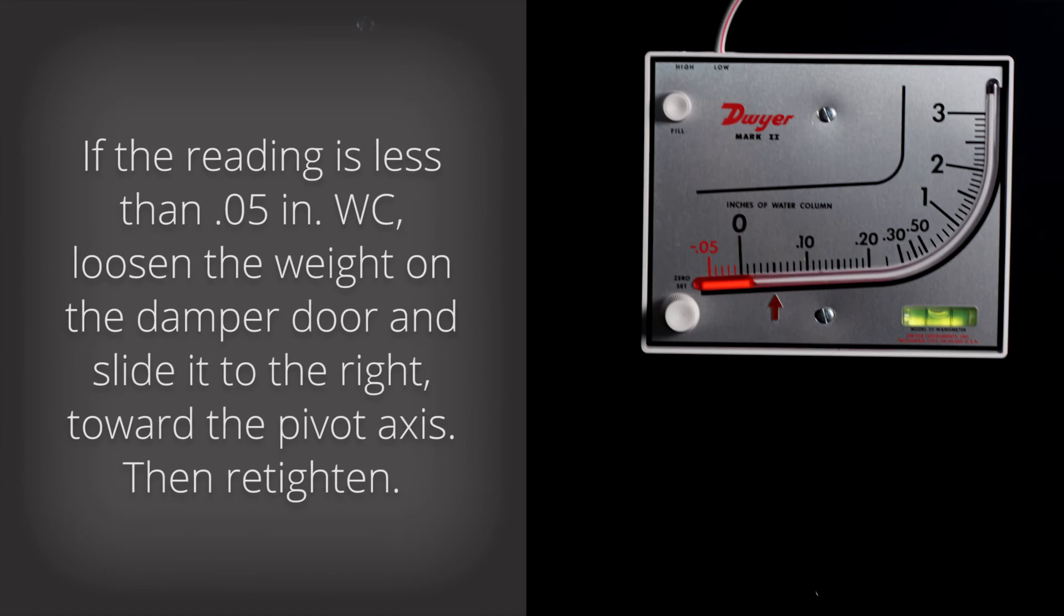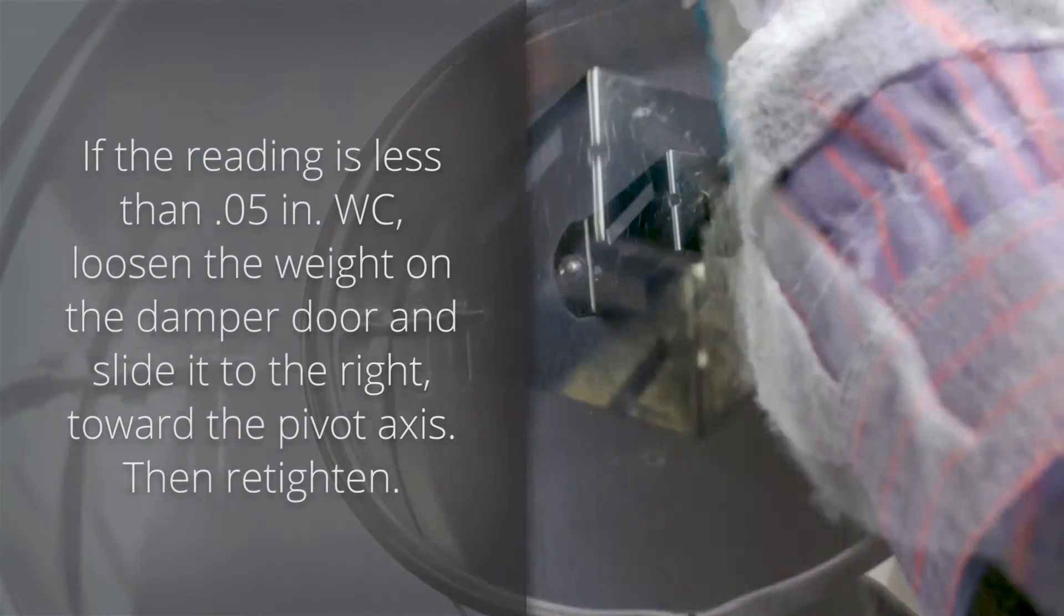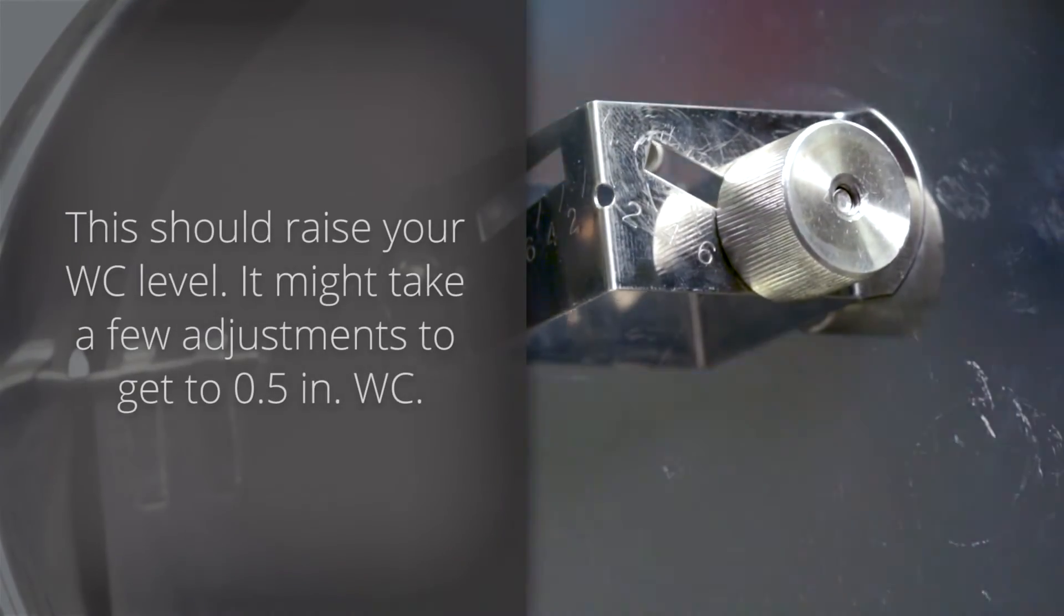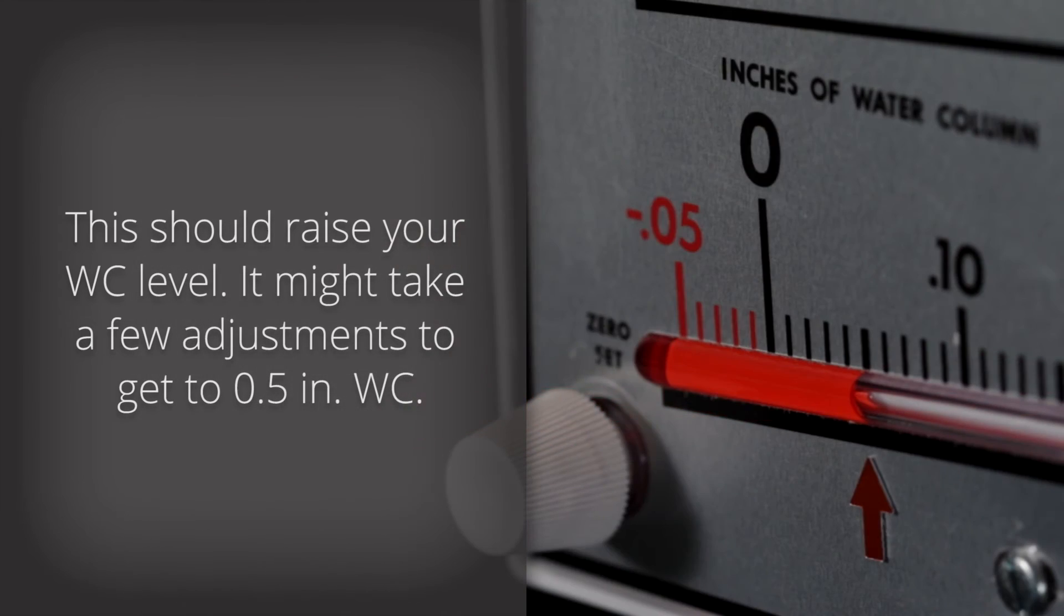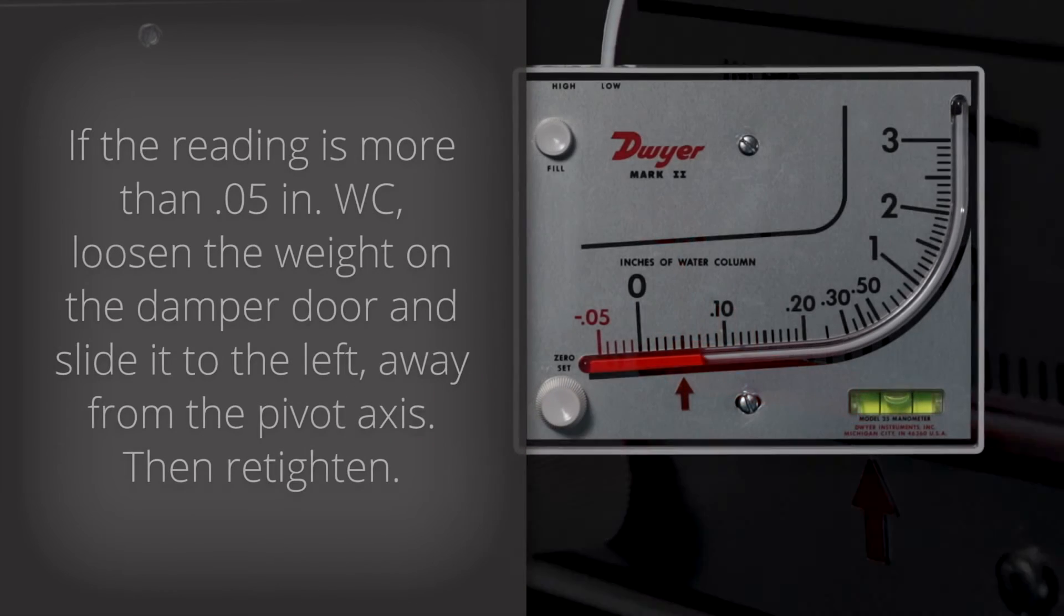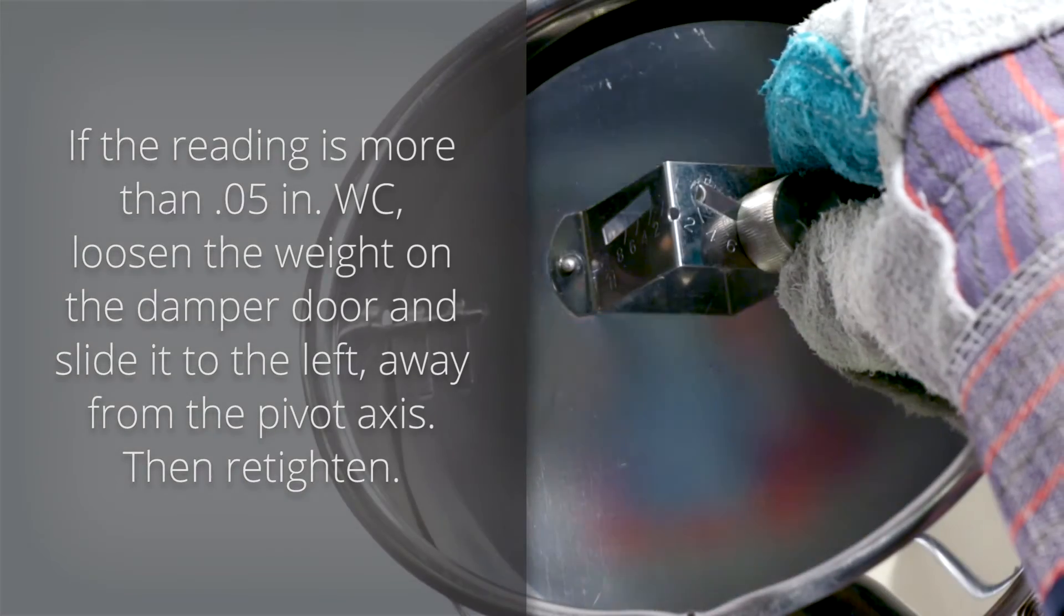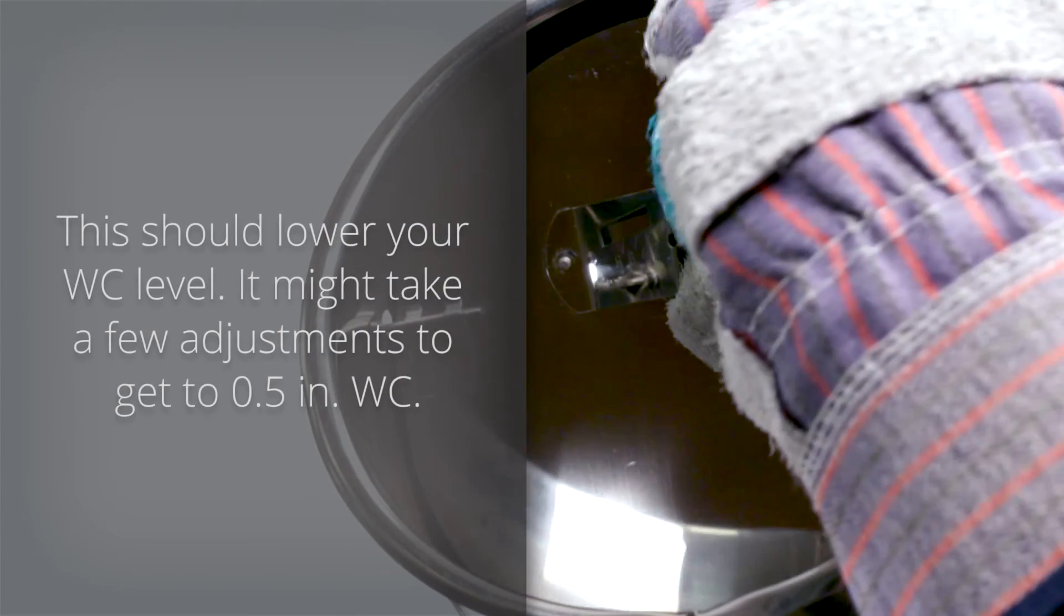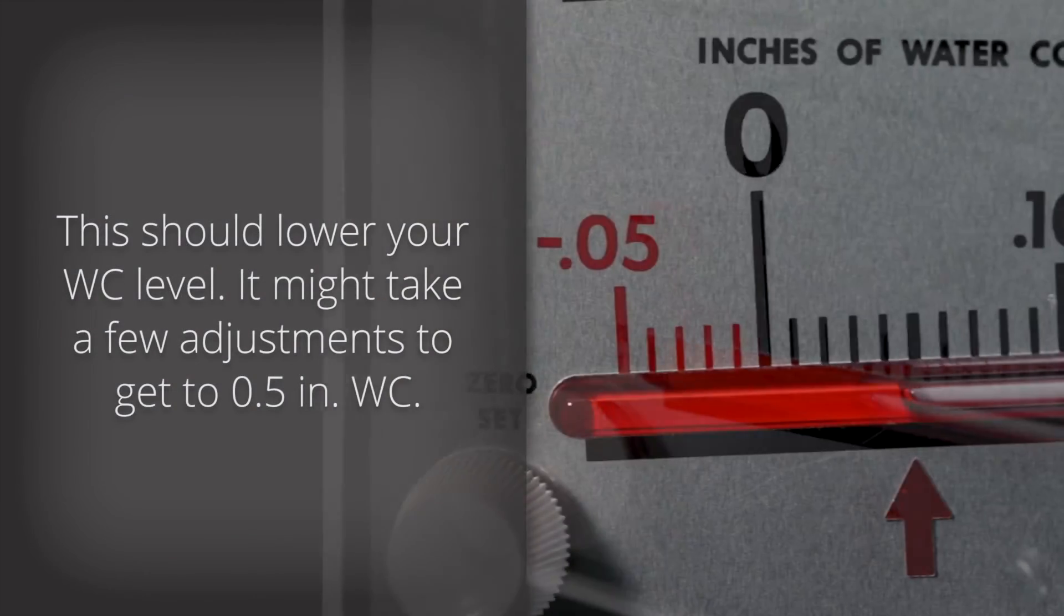If the water column reading is less than 0.05 inches of water column, loosen the weight on the damper door and slide it to the left, away from the pivot axis. Then re-tighten. This should lower your water column level. Again, it might take a few attempts to get to 0.05 inches.